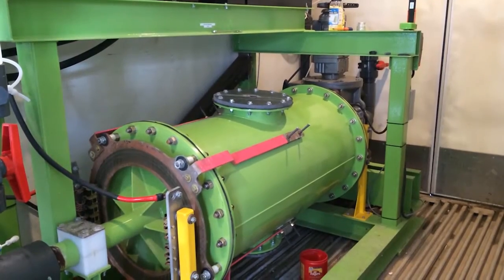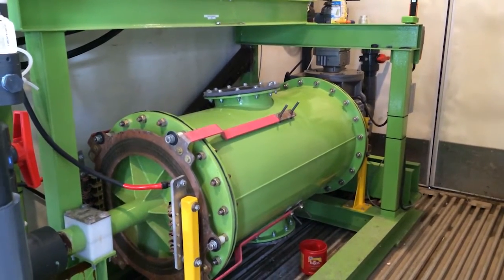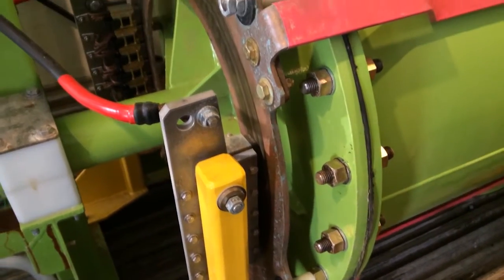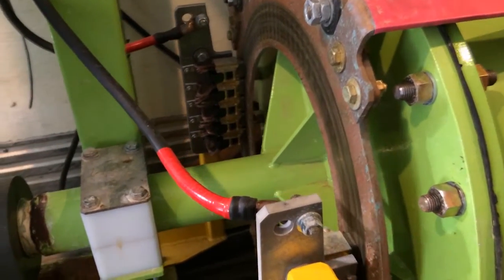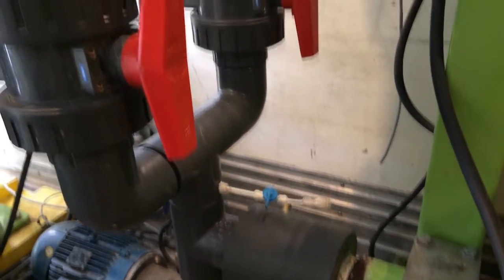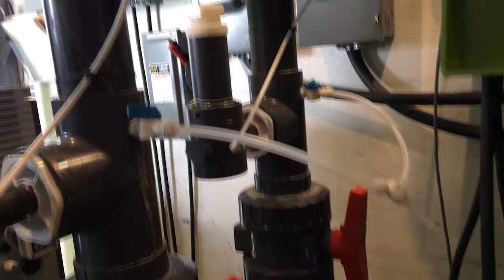As the EC reactor rotates, high-current, low-voltage electricity is transferred from the outside to the inside. The power is transferred from isolated transformers to high-amperage electrical brushes, which in turn pass the power to copper rings and distribution electrical bus bars along the reactor vessel. The treated water exits the EC reactor through a stationary bearing and seal.